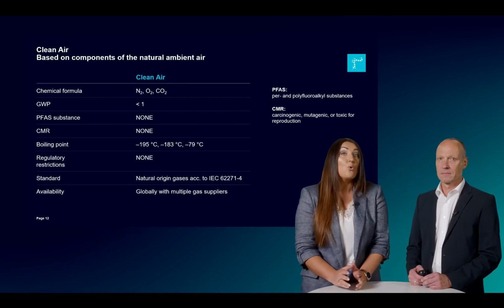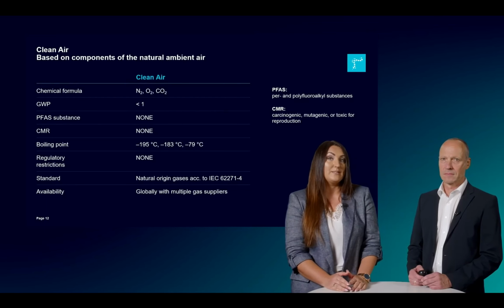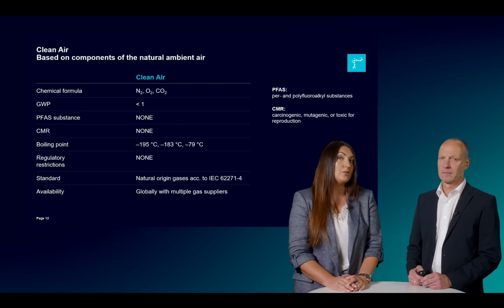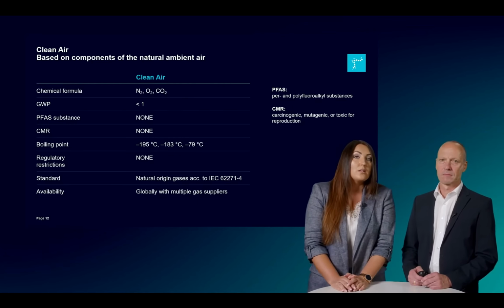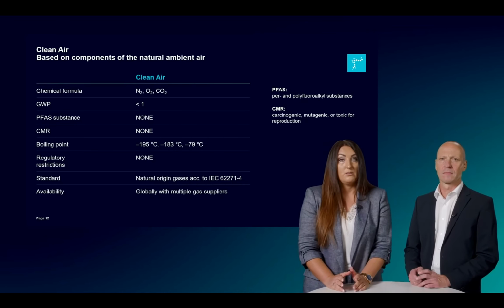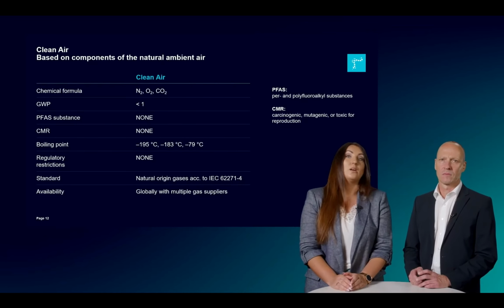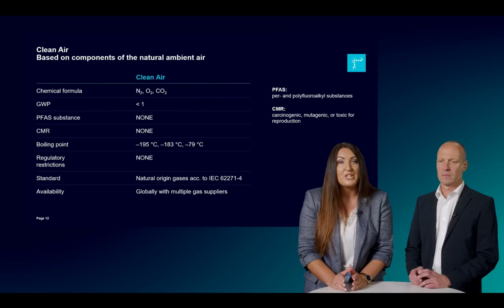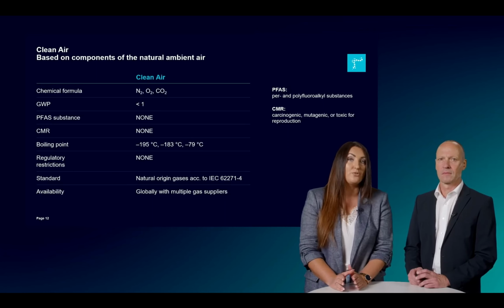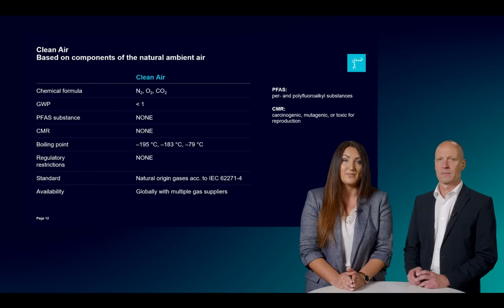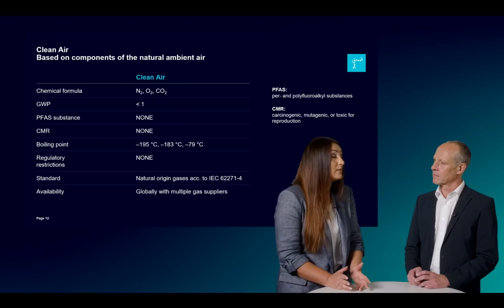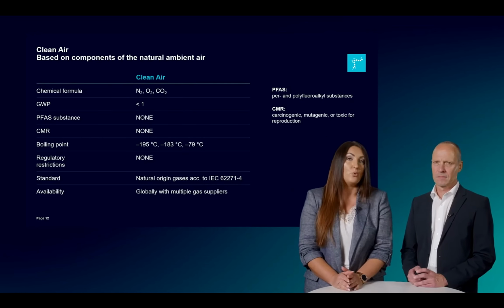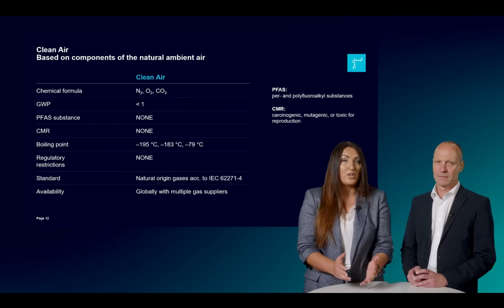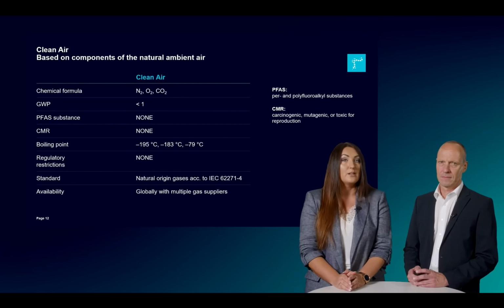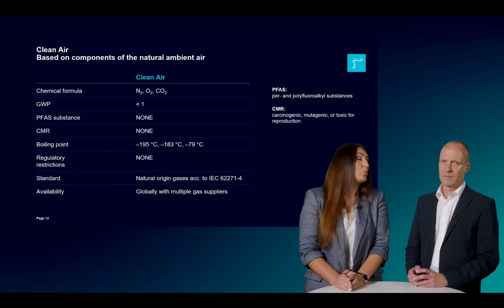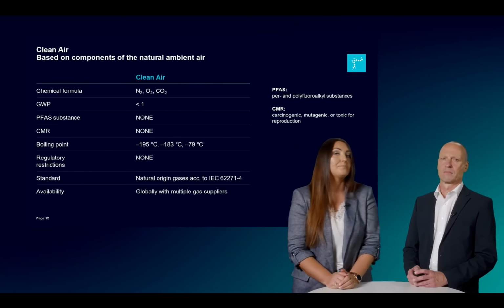And moreover, and also very important, there are no regulations on the documentation or reporting of clean air. Since clean air contains only components of the ambient air, when the switchgear reaches its end of life there is no need for gas recycling as we know it from SF6. Clean air can be released into the ambient air with no issue. So when we consider all this, the switchgear with clean air offers economic benefits throughout its product lifetime.